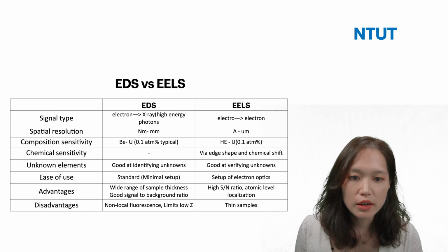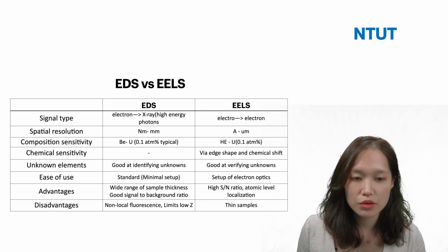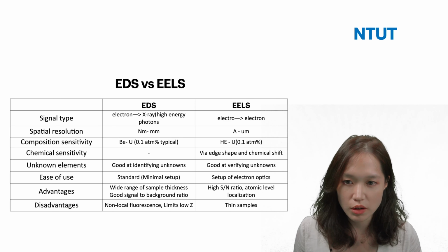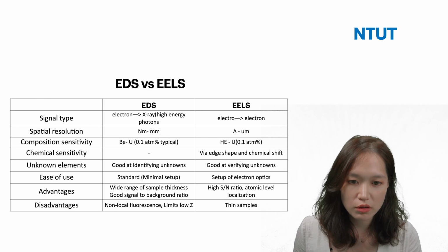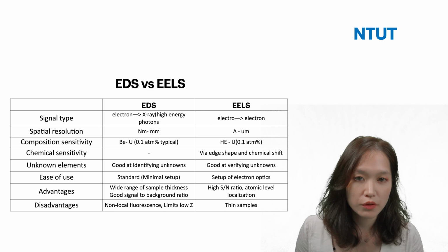And this will reduce the signal to background ratio of the EELS edges. That means we'll reduce the visibility of the edges and reduce the resolution of what we get. However, of course, the spatial resolution of TEM techniques will also be reduced as the thickness increases, losing the quality of the overall thing.